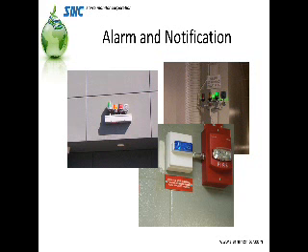One of the things we're seeing more common now is that inside the building, since we're evacuating the building at a lower level than high, we'll see just a white alarm with blue. Note that it does not have the word fire on it, although located next to a fire alarm horn and strobe, it has its own horn and strobe colors to indicate that there is a gas emission. And this typically goes off at 20 to 25% LEL.